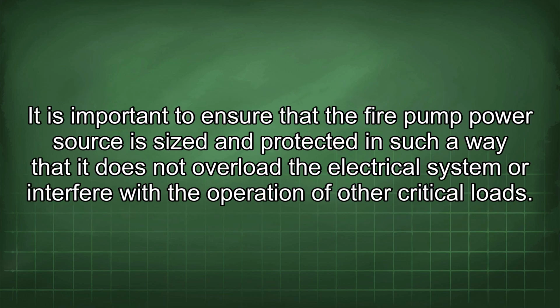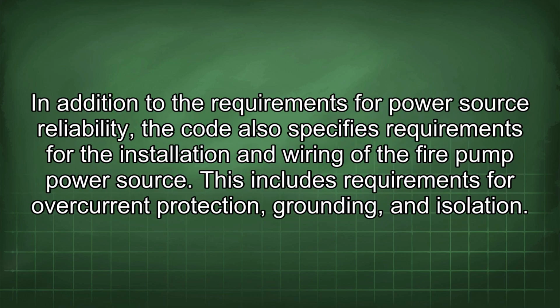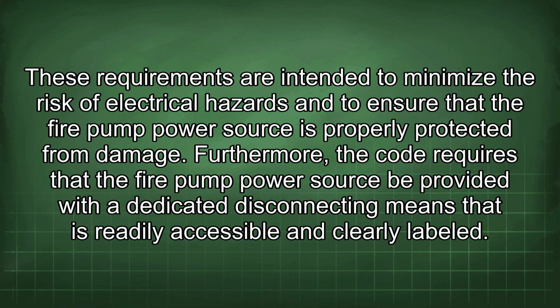It is important to ensure that the fire pump power source is sized and protected in such a way that it does not overload the electrical system or interfere with the operation of other critical loads. In addition to the requirements for power source reliability, the code also specifies requirements for the installation and wiring of the fire pump power source. This includes requirements for overcurrent protection, grounding, and isolation. These requirements are intended to minimize the risk of electrical hazards and to ensure that the fire pump power source is properly protected from damage.